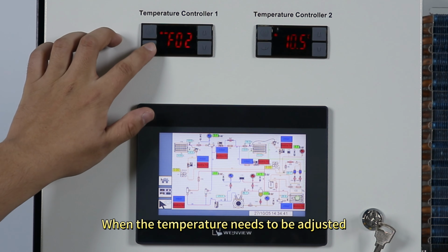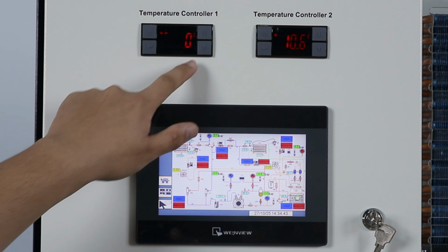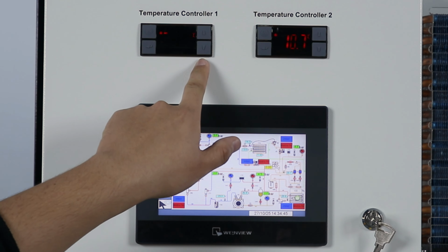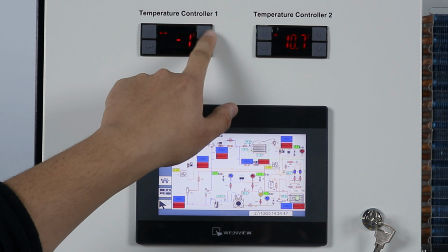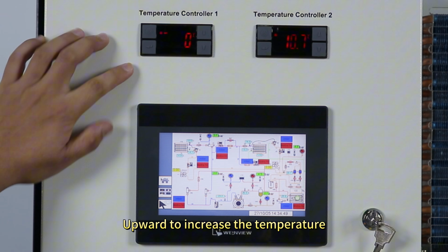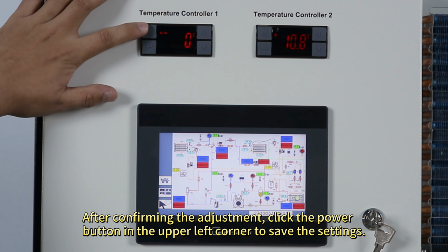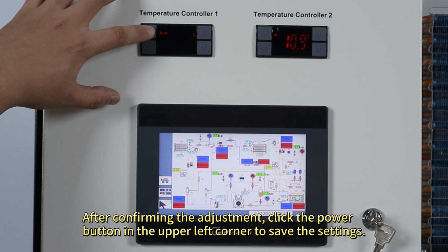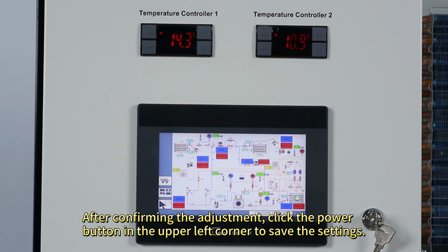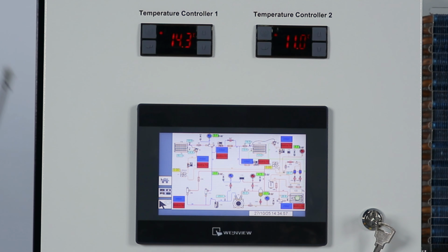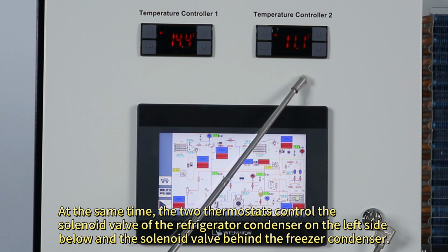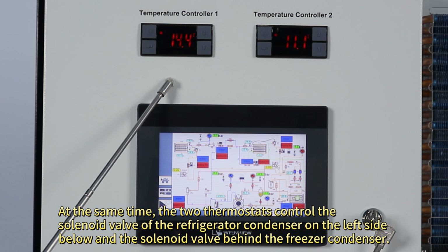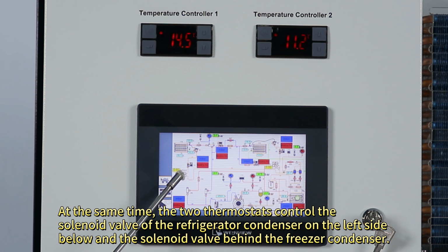When the temperature needs to be adjusted, press downward to lower the temperature, and upward to increase the temperature. After confirming the adjustment, click the Power button in the upper left corner to save the settings. At the same time, the two thermostats control the solenoid valve of the refrigerator condenser on the left side, below, and the solenoid valve behind the freezer condenser.